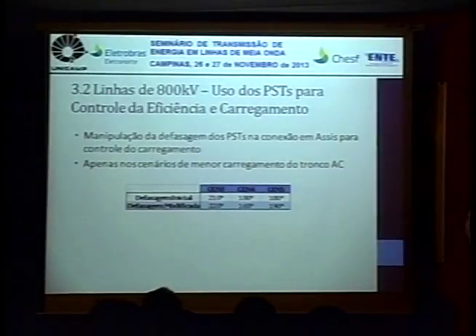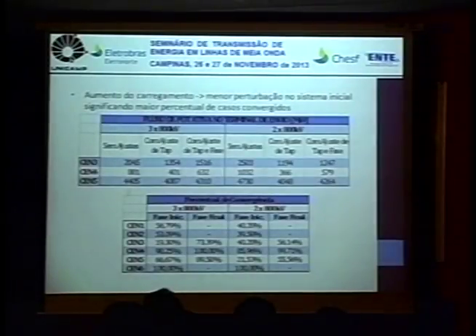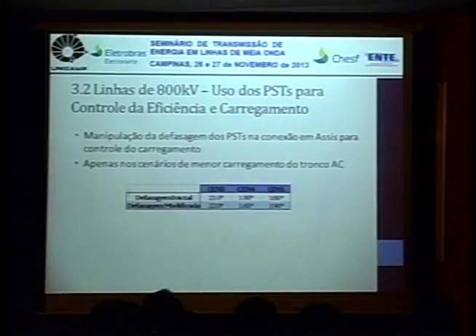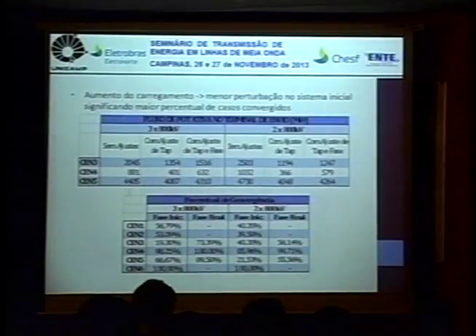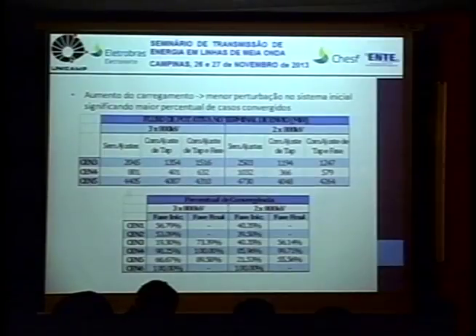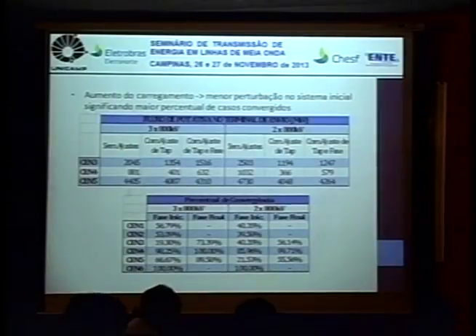But for some scenarios, especially scenarios of light load, it's hard to control the power flow by just adjusting the tap. So we also showed the out of phase angle. We changed it here. It was 210 degrees and went to 220. From 180 it dropped to 165. This is a scenario where south-southeast sends energy to the north, and in another scenario we increased 10 degrees as well. So we calculated, and we can see the impact on the power flow without adjustment is what we had. With the tap adjustment, this is what I got, but I still did not get the flow I wanted. But if I change the out of phase, I can improve, I get this value closer to my reference value.